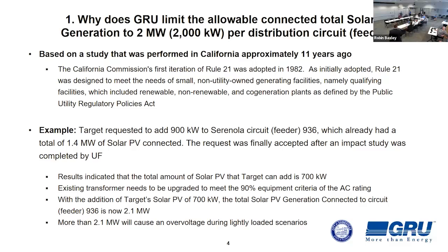So we refused. They were persistent and kept coming back asking what their options were, since they really wanted to maximize their rooftop and install the full 900 kW. Within section 8 of the Energy Delivery Service Guide, there's an option in these situations where the customer can pay for an impact study to determine the maximum amount of solar PV that can be added, or whether they can add the full amount requested.